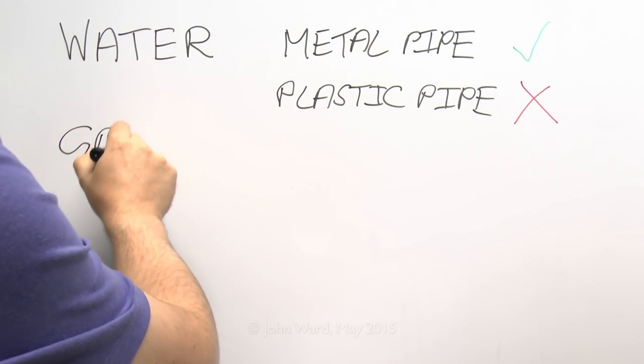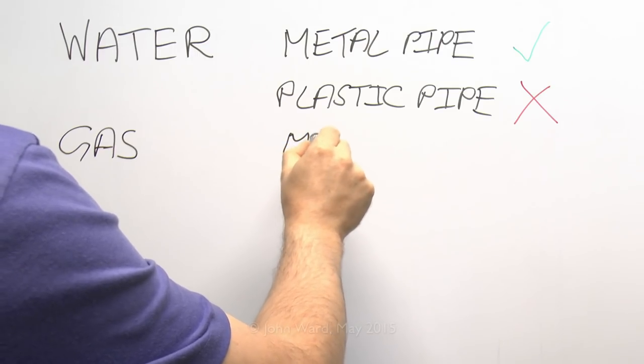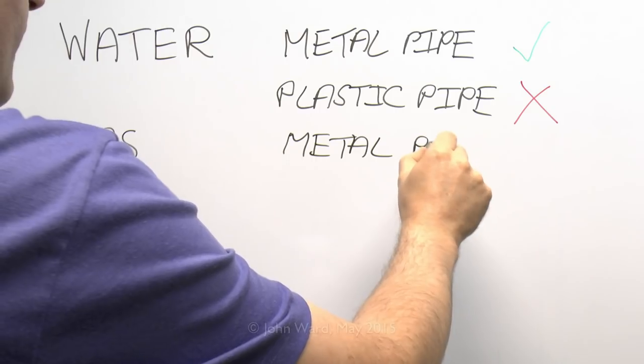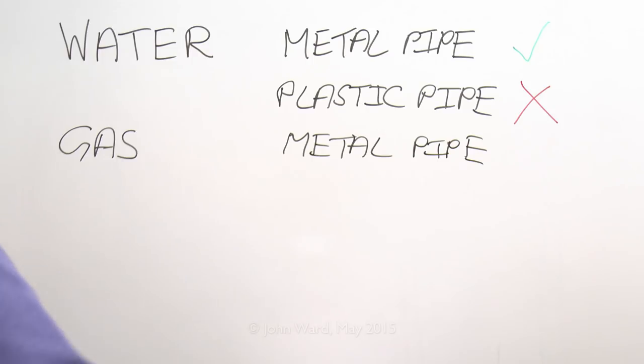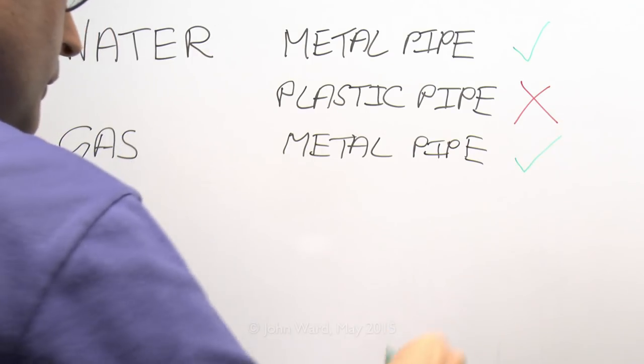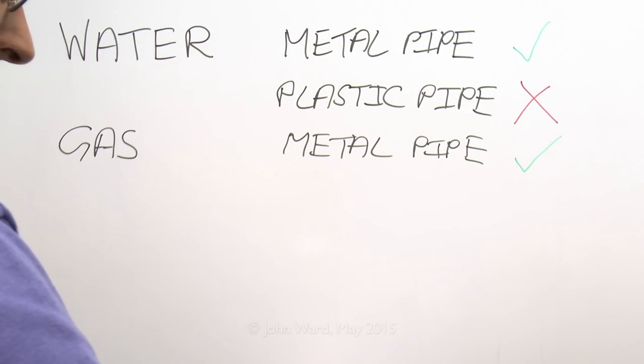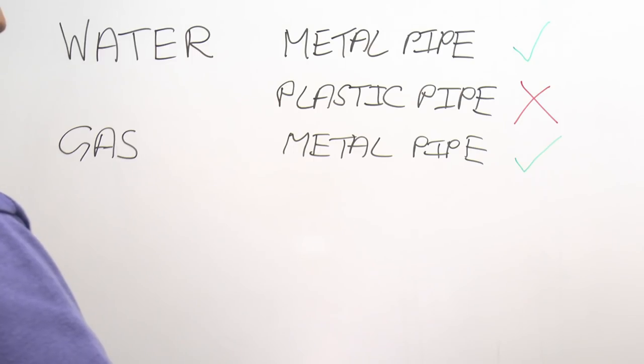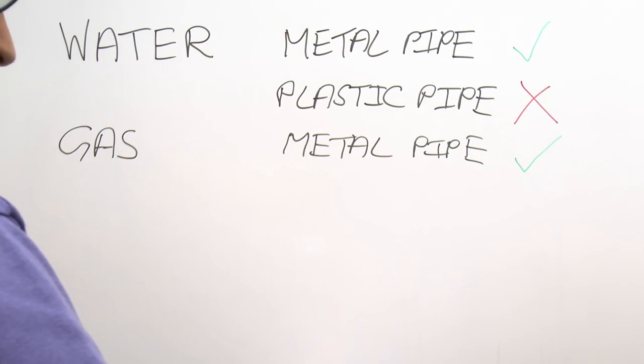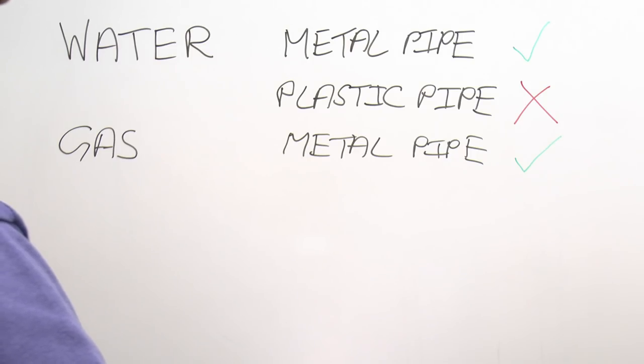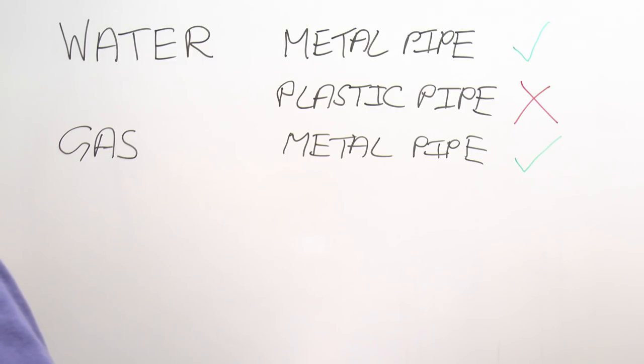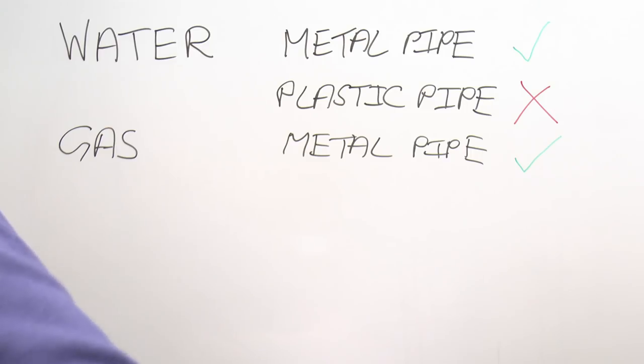Gas is by far the second most common item, and gas is supplied in metal pipes, making it conductive and extraneous, so it needs to be bonded. Gas pipes in the street are frequently plastic these days — generally yellow — but those plastic pipes do not come into the building. The pipes coming into the building will be metallic, so the likelihood of a plastic gas main in your house is essentially zero. The pipes inside the building for gas will not be plastic either — they're always going to be metal.